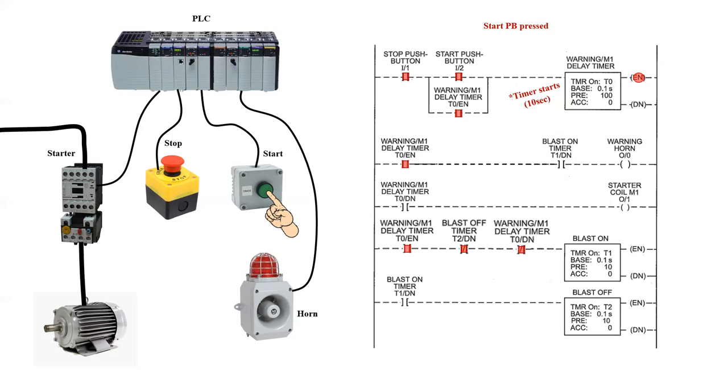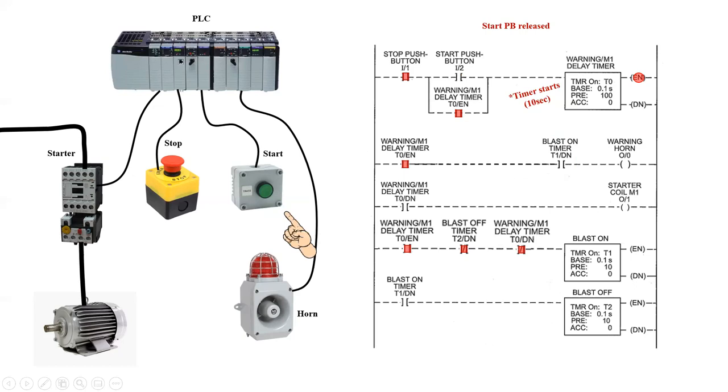At the exact same time, all of the internal bits that the enable coil controls will go true. This includes a holding path for my start push button, which means I can now release my finger from the start push button, and the timing sequence is started.